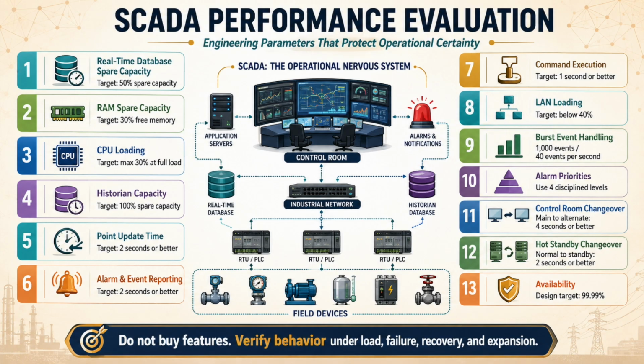A minimum 100% spare historian capacity is sensible because history always grows through more points, higher sampling rates, longer retention, calculated values, event-based logging, reports, analytics, alarm journals, backfill, and store and forward records.